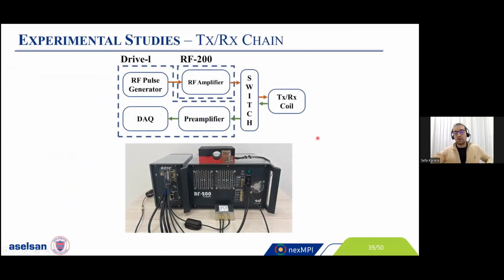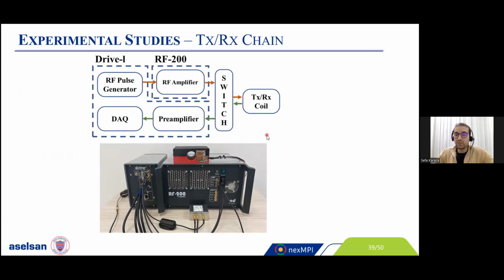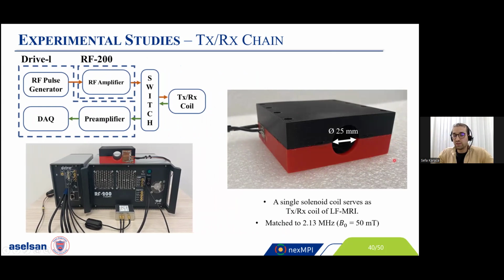At the beginning, I showed you four different coil groups. By using those coil groups, we can generate the B0 field of MRI and the gradient fields, but we cannot generate the B1 field, the radio frequency field. We add those parts by using the Drive-L control unit and the RF-200 amplifier of pure devices. We add a single solenoid coil for both transmission and reception of the LF-MRI signal. Again, we are trying to perform MRI at 50 millitesla, corresponding to a Larmor frequency of 2.13 megahertz.